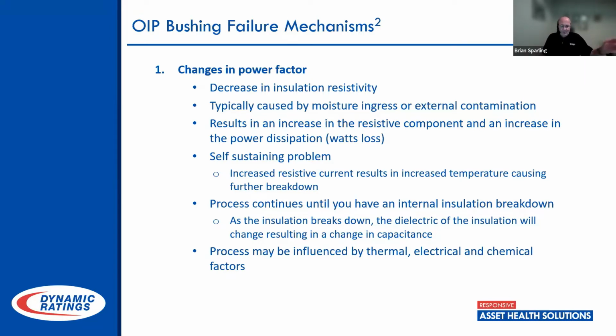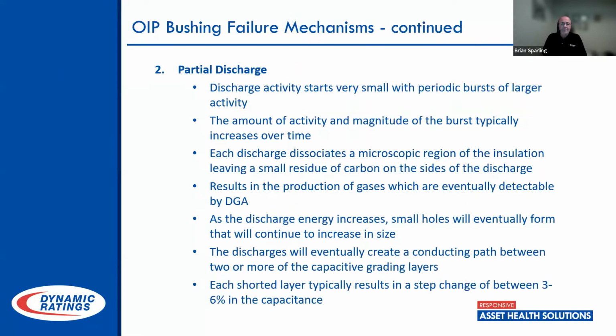That's more or less the process. There's also, with moisture inside, the evidence and opportunity for partial discharge to begin inside the bushing insulation system itself. And it's difficult to detect because the PD inside a bushing or inside a transformer is very periodic bursts of larger activity. And the amount of the activity is typically related to the location and also the amount of material involved in that particular area.